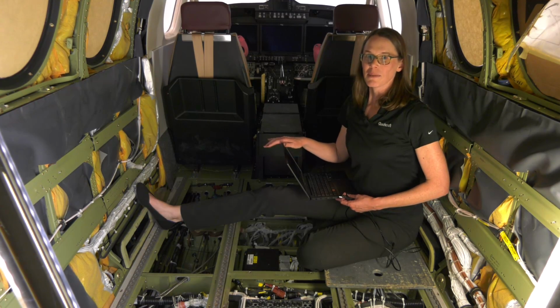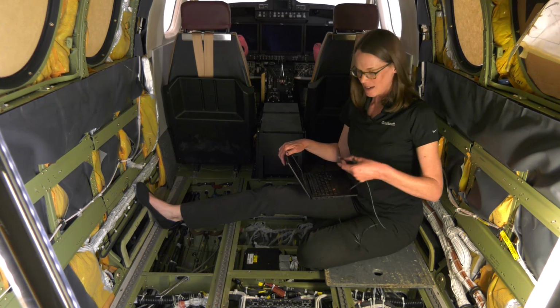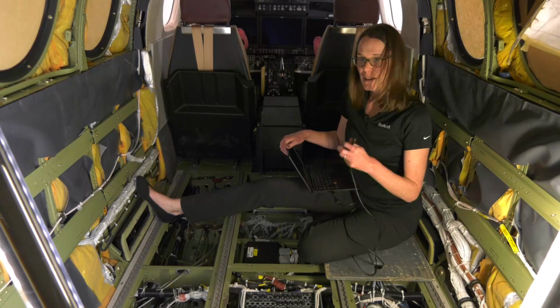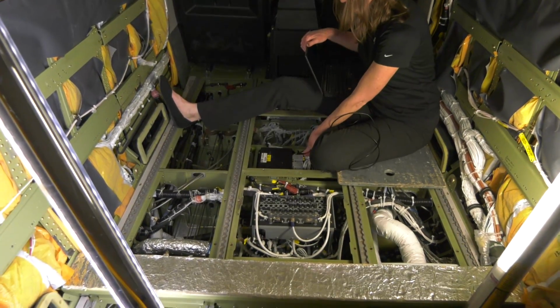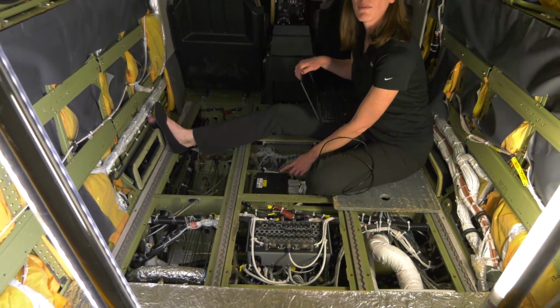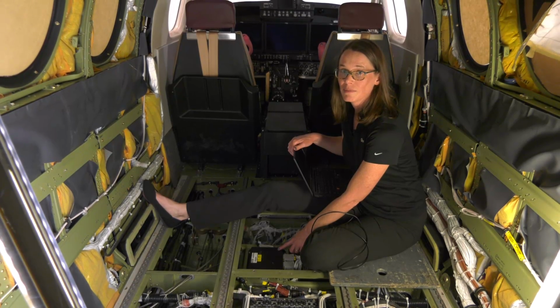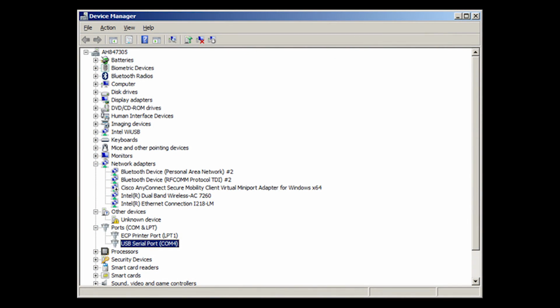Make sure your laptop is completely booted up. The Type A connector goes to your laptop, and the Type B goes to the environmental controller. The light on the environmental controller will tell you that it's powered on. Verify the COM port number on your computer's Device Manager. This can be found by searching Device Manager from the Start menu. Expand the Device Manager menu for Ports COM and LPT. Note the number of the entry in the USB serial port. This will be used to set up PuTTY in the next steps. It may change each time you connect.